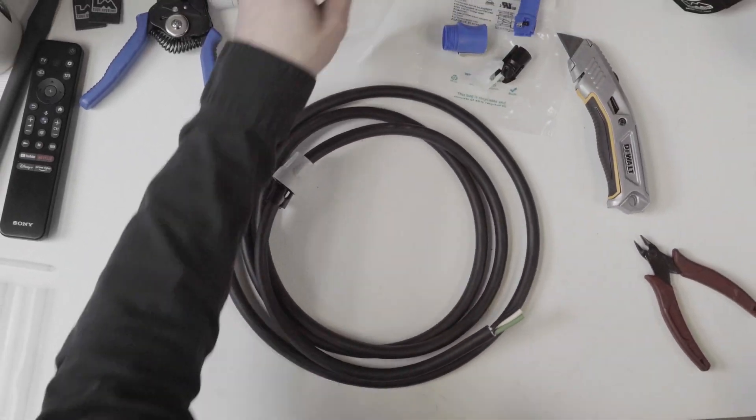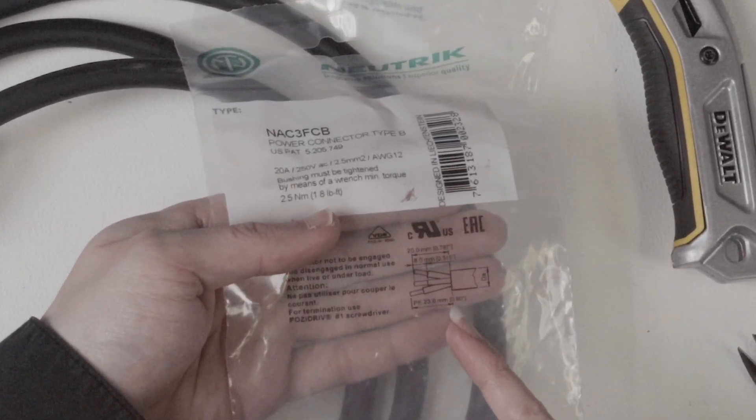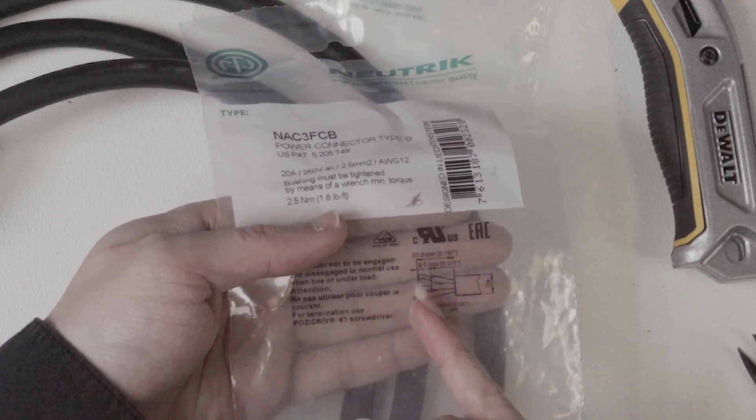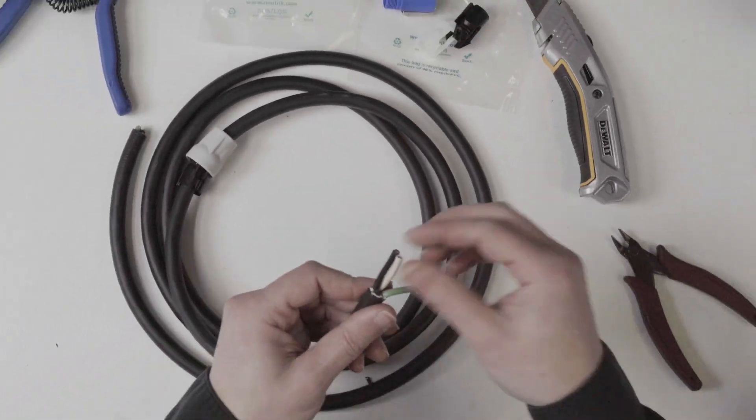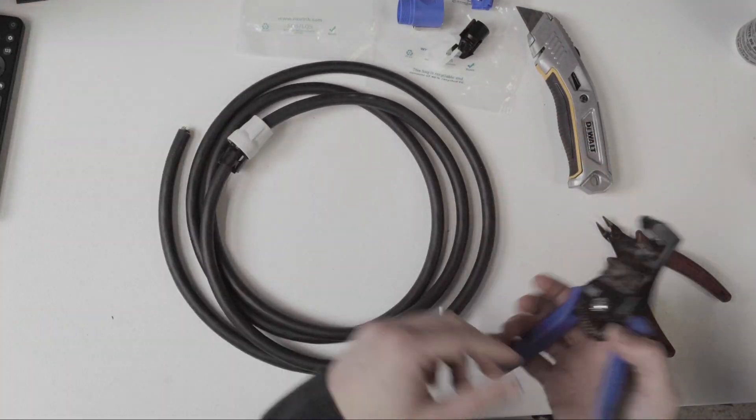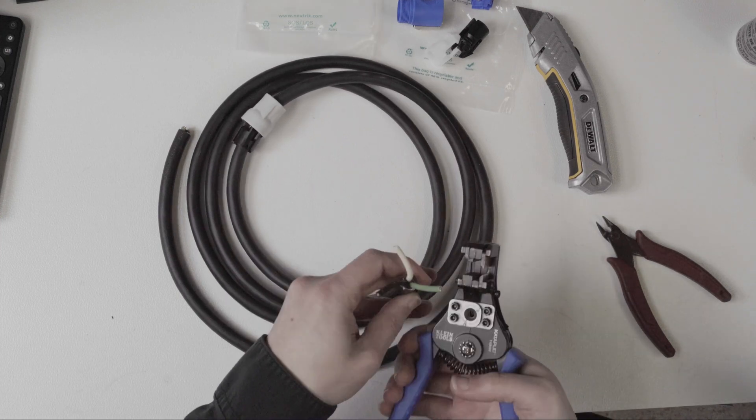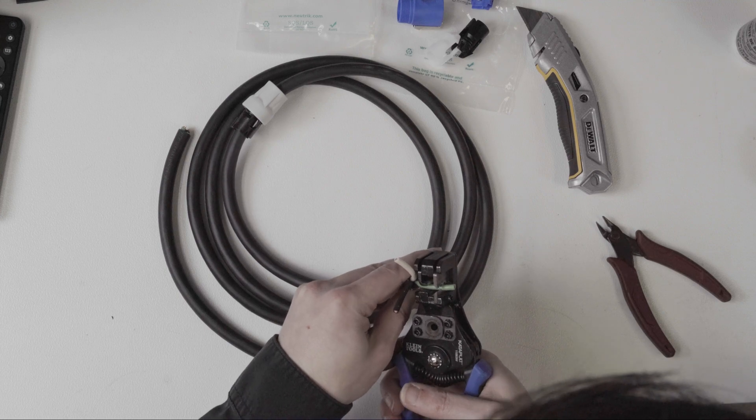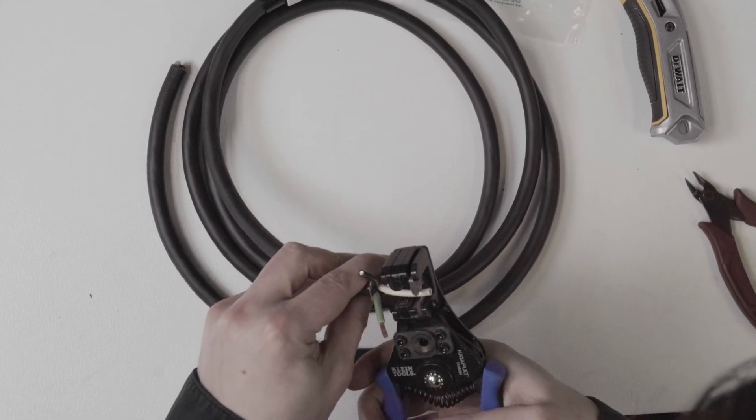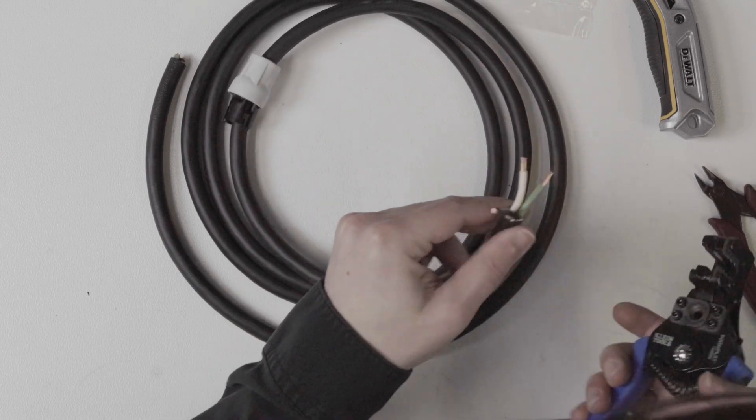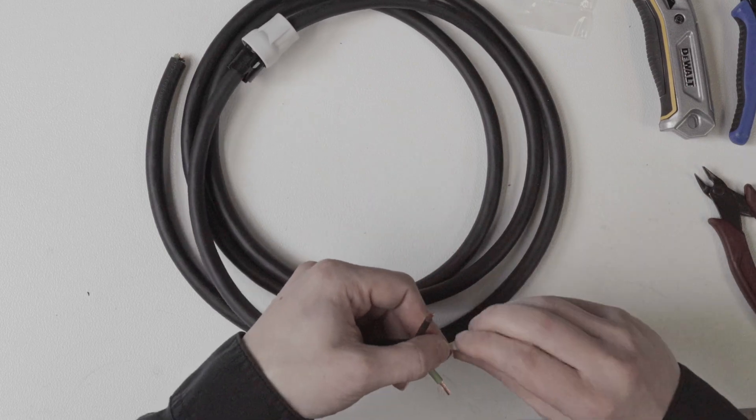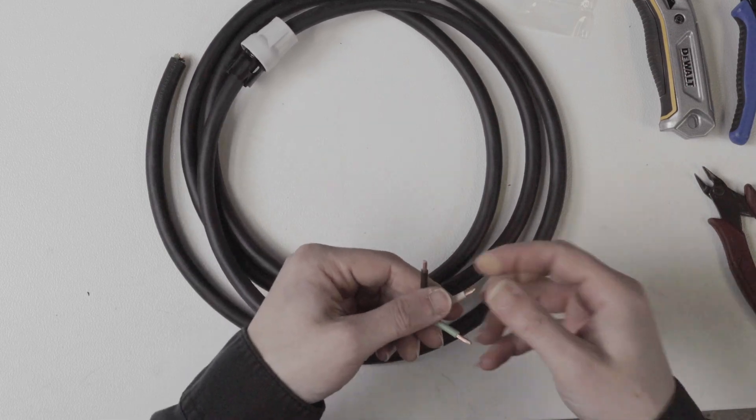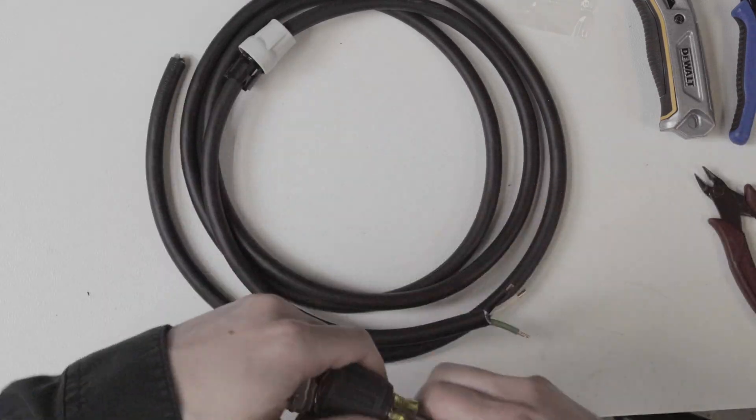So if you do look at the bag that this came in it does give you they want you to strip 23 millimeters and each of the conductors need to be stripped eight millimeters. So before anybody mentions that in the comments section I know I just build a lot of these so see how close I get. So I'm just gonna use my little Klein Katapult tool here and this is 12 gauge cable.